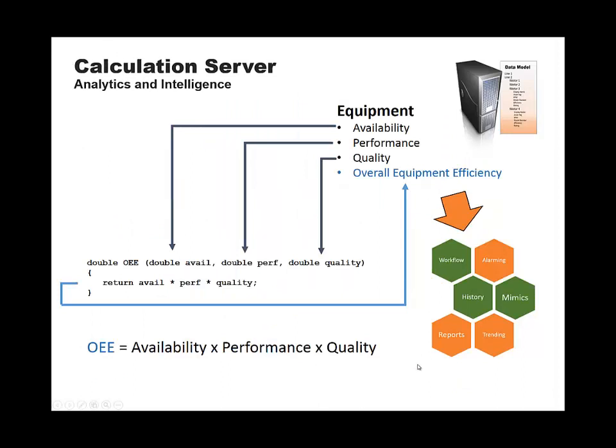For analytics, we have a calculation server with a couple hundred different calculations in the software. The way a calculation works is fairly simple: you define a calculation — or use one of the calculations provided by BSCADA — and if you have a type in your model, you can use a few of the properties as input into the calculation. The output of the calculation will go back out to another property in the model. That calculated value is just another value in the model, so it can be used in alarms, reports, the historian, trends, and workflow.